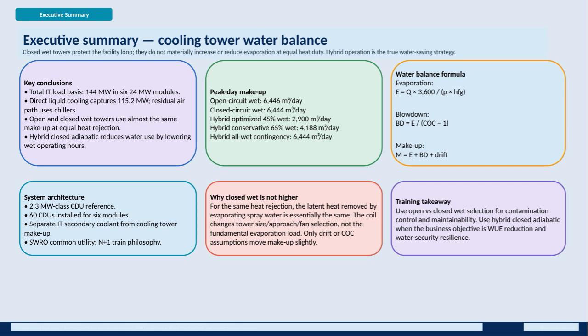The water balance formula essentials break down into 3 parts: evaporation, blowdown, and makeup. Evaporation depends on the heat rejection, the density of water, and the latent heat of vaporization. Blowdown is calculated based on evaporation and the cycles of concentration in the system. Makeup water is the sum of evaporation, blowdown, and drift losses.